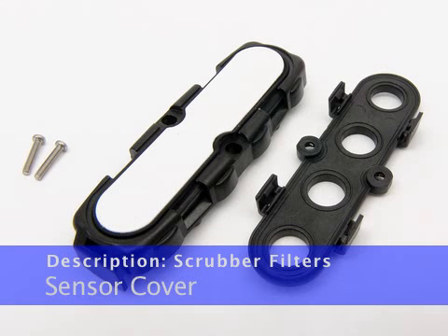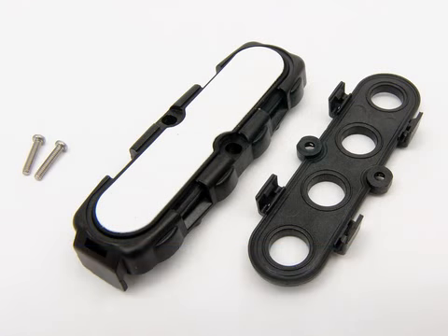The sensors are protected from the environment by the sensor cover, which allows ambient air to diffuse to the sensors. The sensor cover is white and protects the scrubber filters and sensors from dust and water. It fits on the sensor retainer gasket over all the sensor diffusion ports and is secured in place by the sensor cover retainer. If the sensor cover becomes dirty, the response time and accuracy of the GX-2009 will be affected. Replace the sensor cover if it appears dirty.